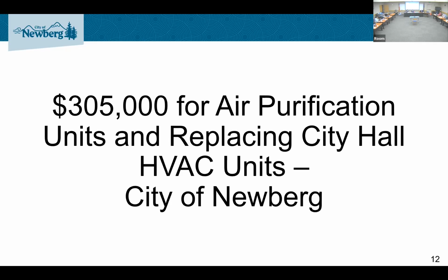The second component of that is the City Hall HVAC system. City Hall, as many of you might be aware, burned down back in the 90s. At that time, it was completely reconstructed and 2 HVAC units were put on the roof, 2 25-ton units. Those are the original units that are still there today. One unit has completely failed. And we've actually been fortunate in having our maintenance contractor, Alliant, come in and fix it to the point where it's fixed operation. It's not economical to run, but it's running continuously 24/7. There's no on-off switch. It's wired on.